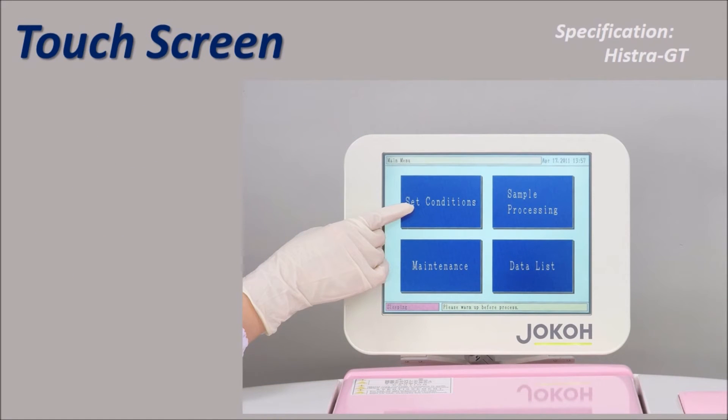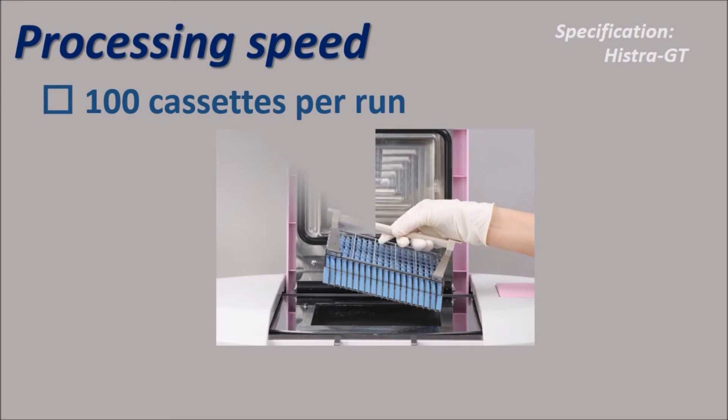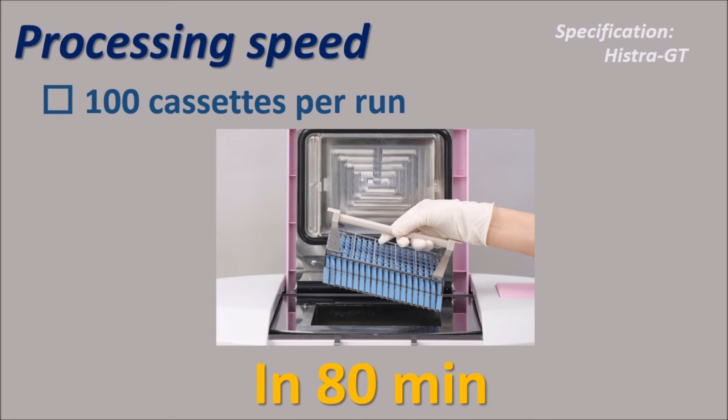Jokoh Histra-GT has a large touch screen that enables easy operation of the instrument. It is a rapid processor using ultrasonic — for 100 cassettes, only 80 minutes of processing time is needed. The program can be set for both normal processing and rapid processing depending on your need.